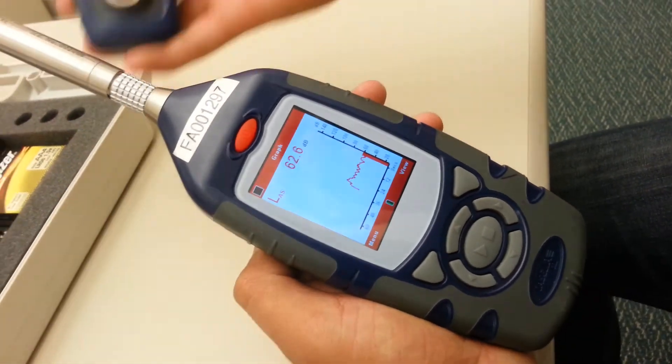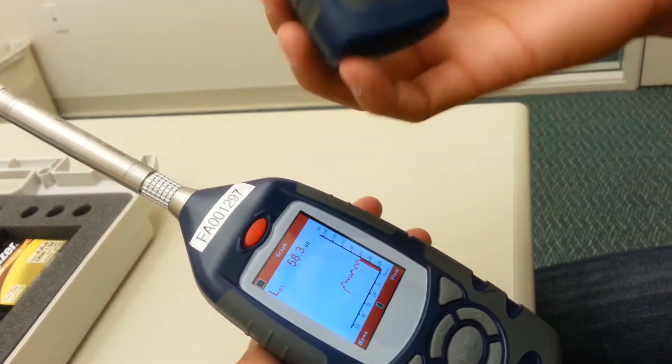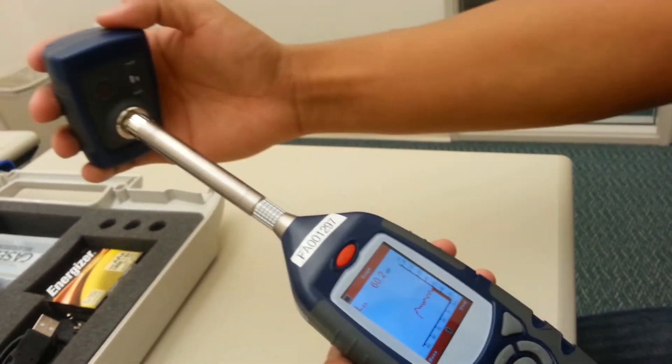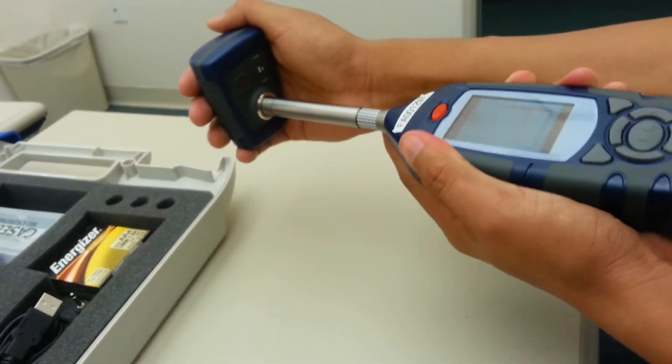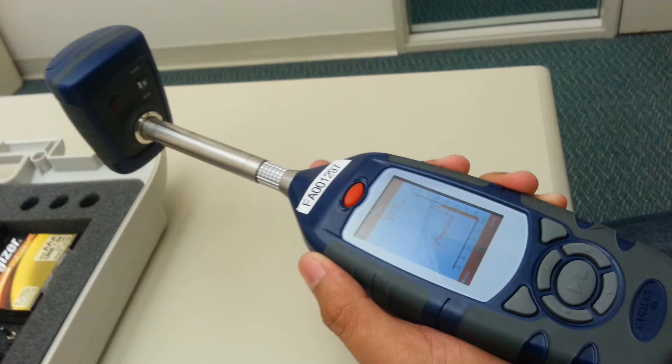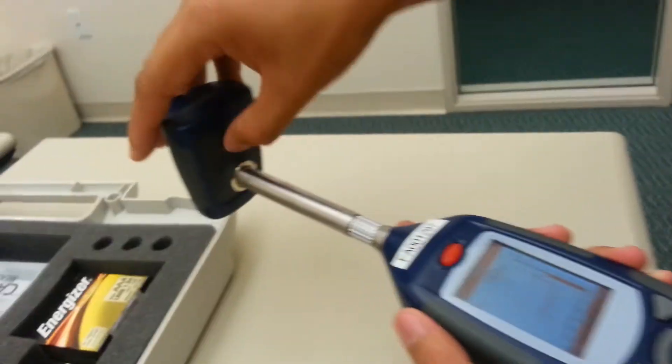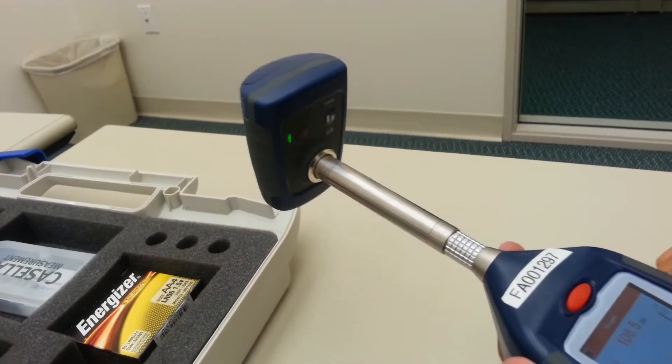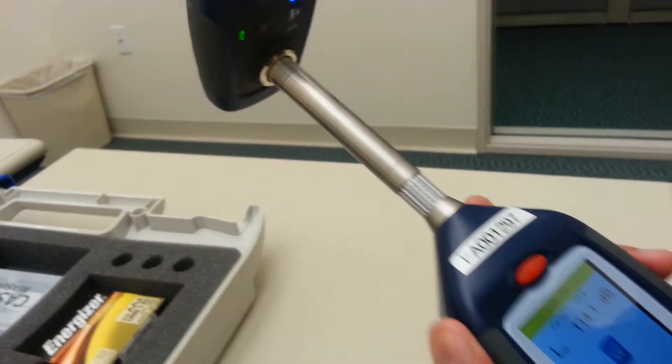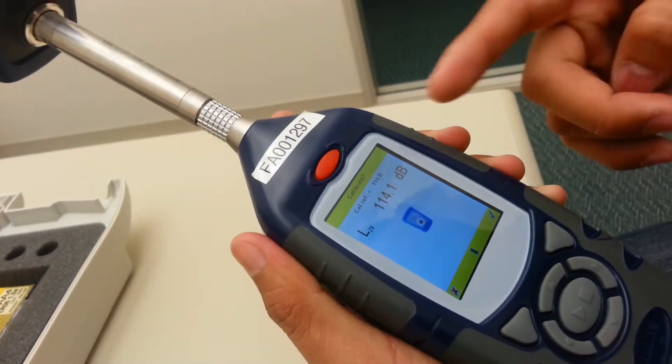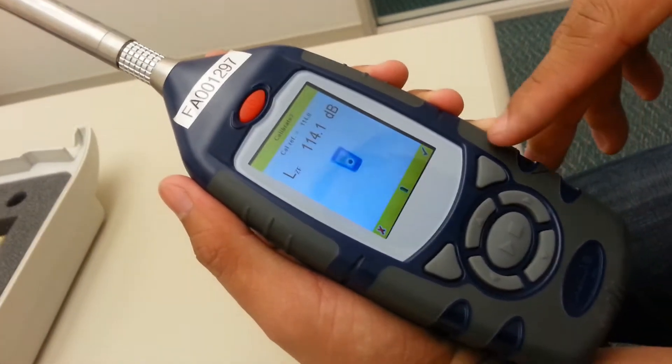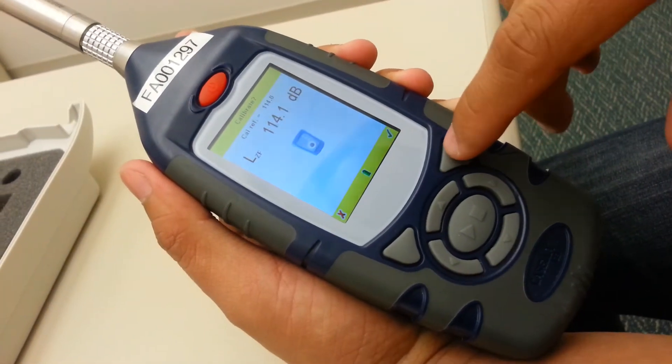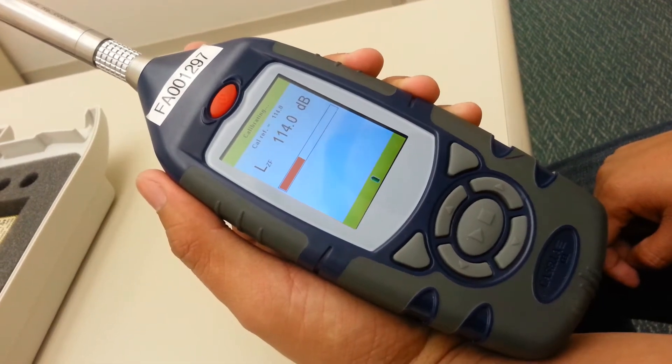You'll attach the calibrator onto the microphone as such, all the way in. And you'll click the on button right here and hold it until it turns green. Once you do that, you'll notice on the sound level meter, it will ask you to calibrate. You'll press the check mark.